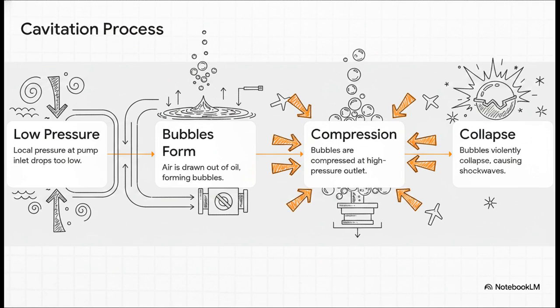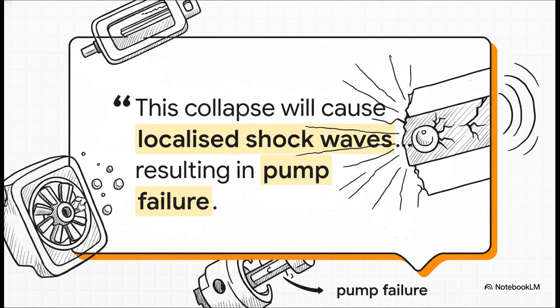Step 3, these harmless-looking bubbles get swept right into the pump and are rapidly compressed in the high-pressure region at the pump's outlet. Finally, step 4: under that immense pressure, the bubbles violently collapse. Let me emphasize the massive stakes of this process by reading a direct quote from our source material. It says this collapse will cause localized shock waves to impact the subcomponent surface within the pump, resulting in pump failure.